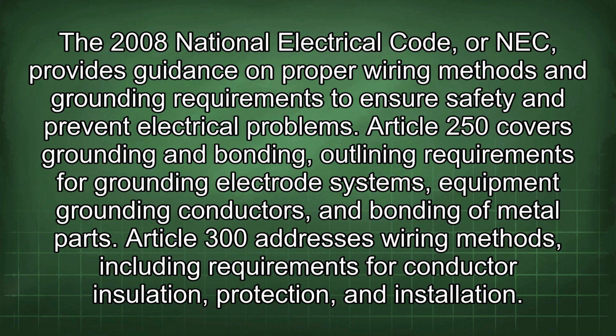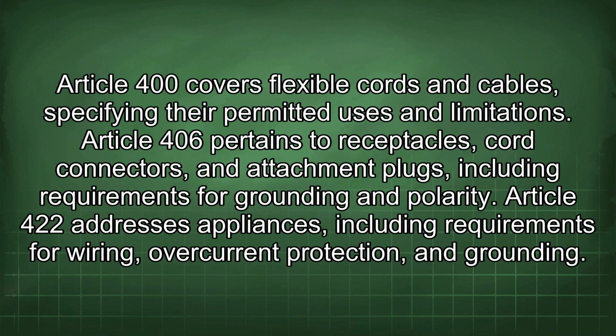and prevent electrical problems. Article 250 covers grounding and bonding, outlining requirements for grounding electrode systems, equipment grounding conductors, and bonding of metal parts. Article 300 addresses wiring methods, including requirements for conductor insulation, protection, and installation. Article 400 covers flexible cords and cables, specifying their permitted uses and limitations. Article 406 pertains to receptacles, cord connectors, and attachment plugs, including requirements for grounding and polarity.